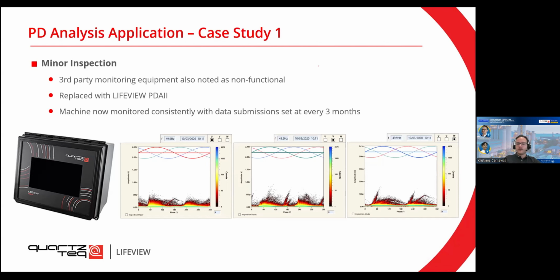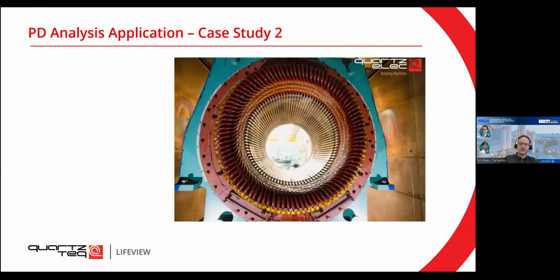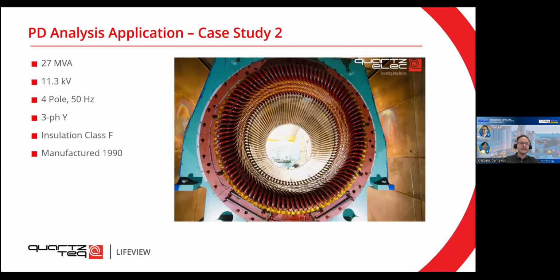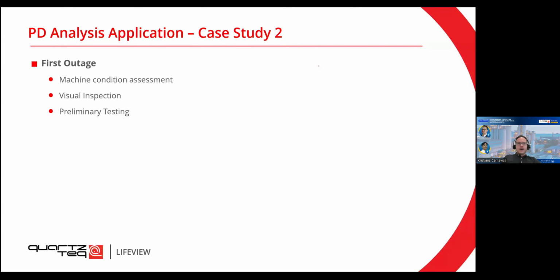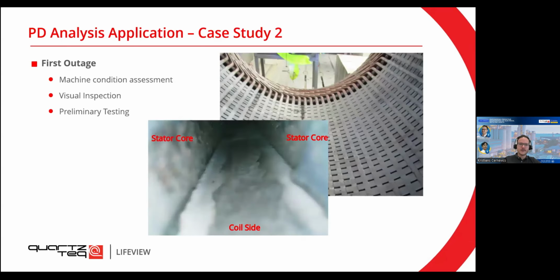Okay, and then for the last one, case study number 2, this is a lot older machine, 1990, I think also an 11 kV machine, 4 poles, 50 hertz. On the outage, machine condition was assessed. There was a visual inspection and also preliminary testing. And what was discovered was that there's a lot of spark erosion. So a lot of partial discharge activity must have happened before, so that visually it was already detected.